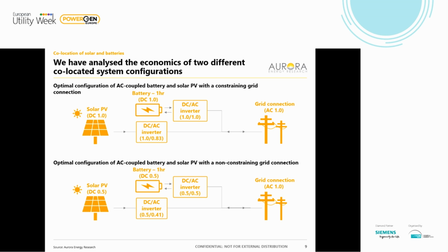What we've analyzed with them is a whole bunch of different configurations of how you can co-deploy solar with battery. We're showing two optimal configurations: one with a constraining grid connection, where the grid connection is smaller than the sum of your solar plus battery, with DC to AC oversizing of solar at 1 to 0.83. Below that is the optimal configuration without oversizing, where the grid connection size matches the sum of the capacities of battery and solar.